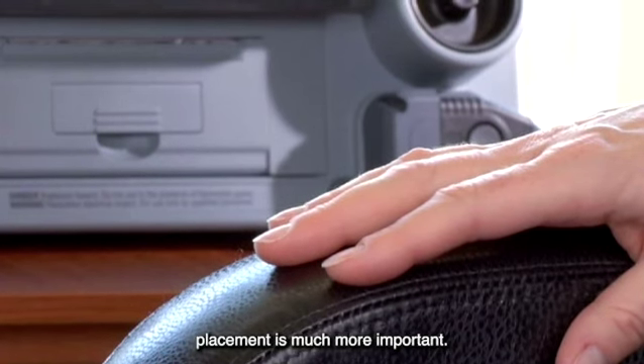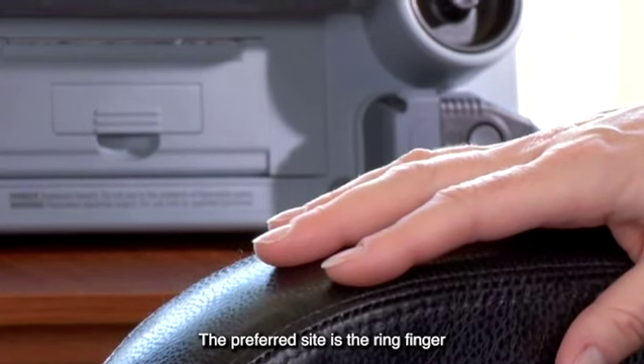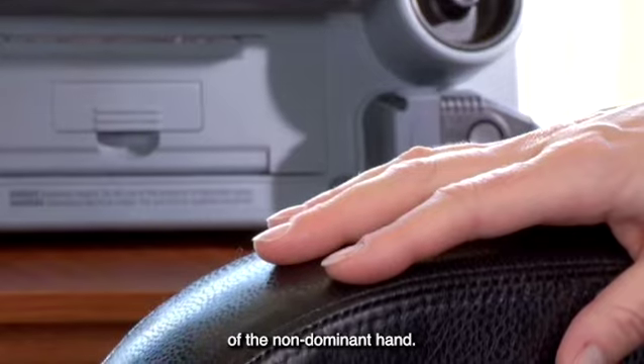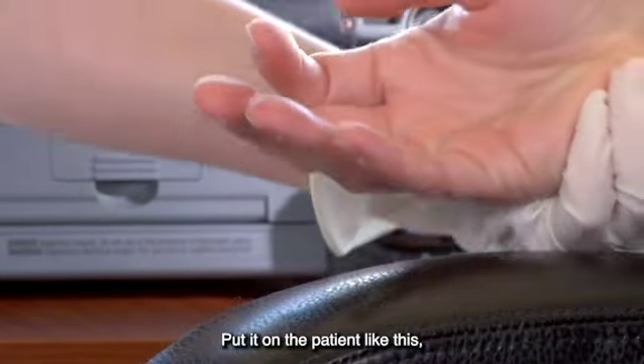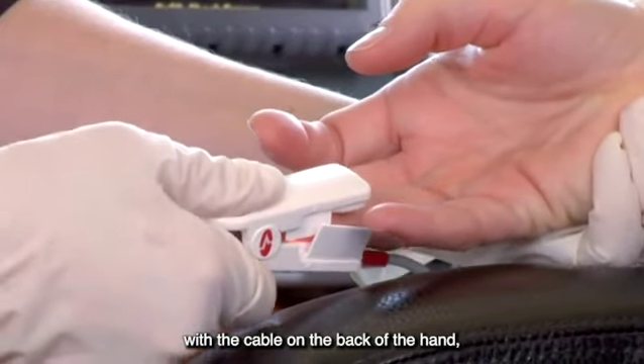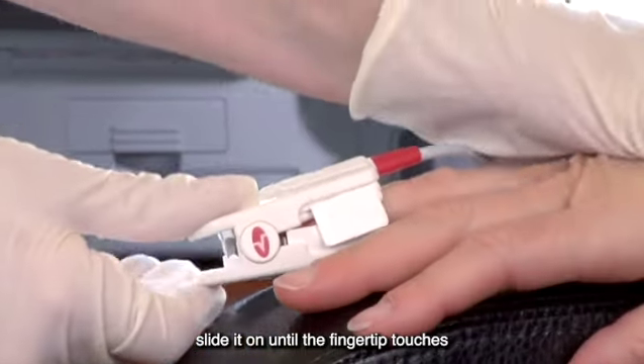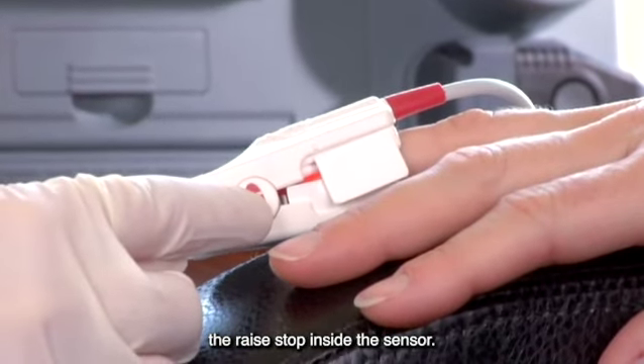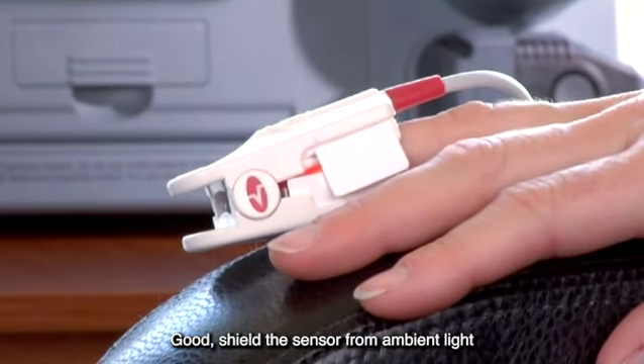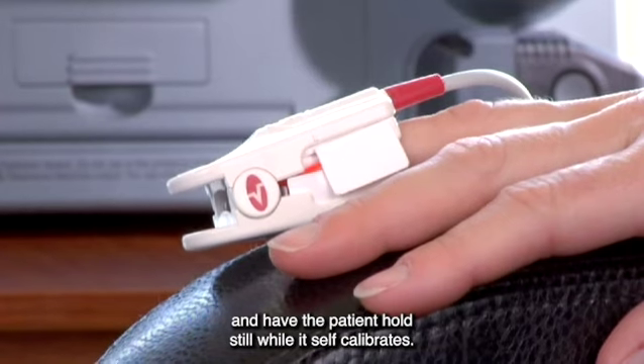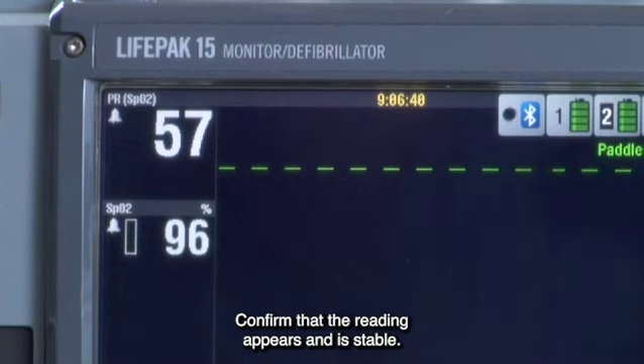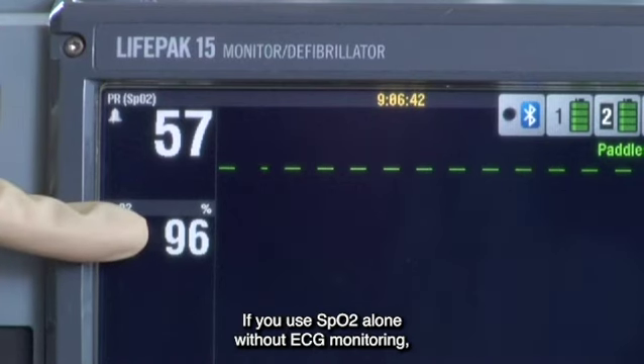is much more important. The preferred site is the ring finger of the non-dominant hand. Put it on the patient like this, with the cable on the back of the hand. Slide it on until the fingertip touches the raised stop inside the sensor. Good. Shield the sensor from ambient light and have the patient hold still while it self-calibrates. Calibration can take 15 to 30 seconds. Confirm that the reading appears and is stable.